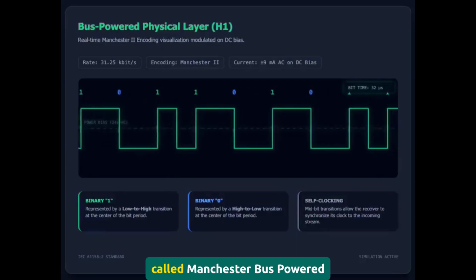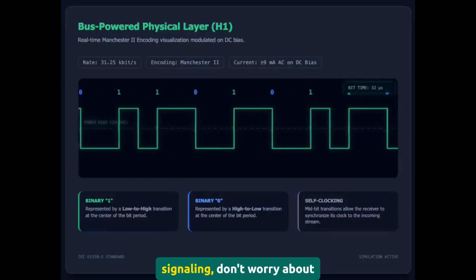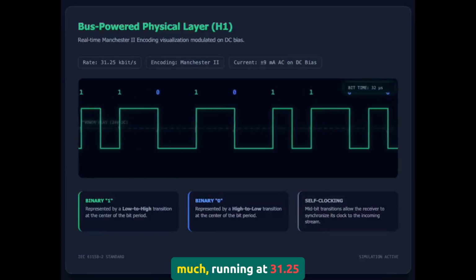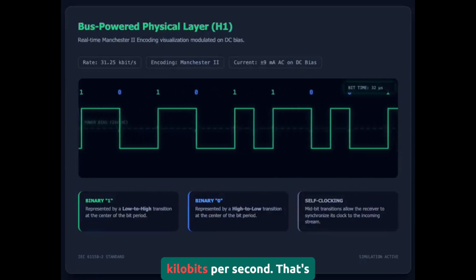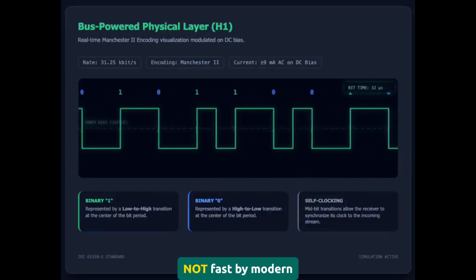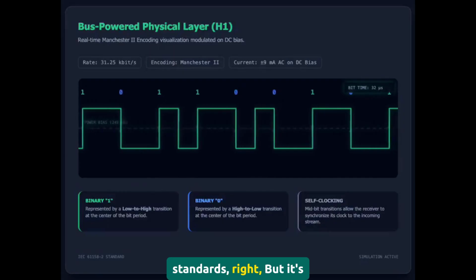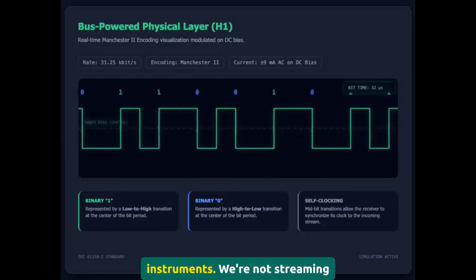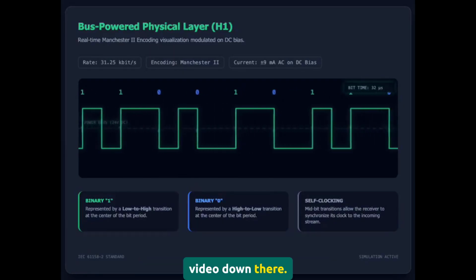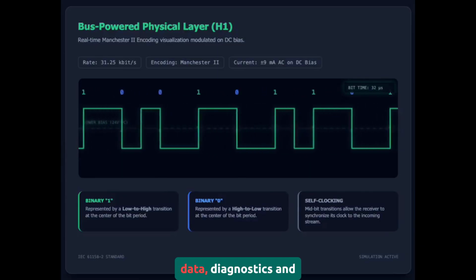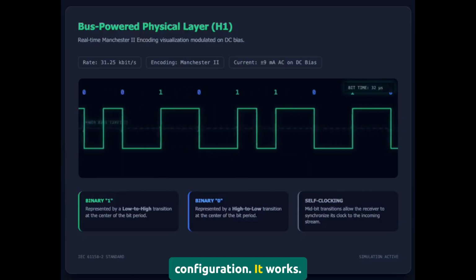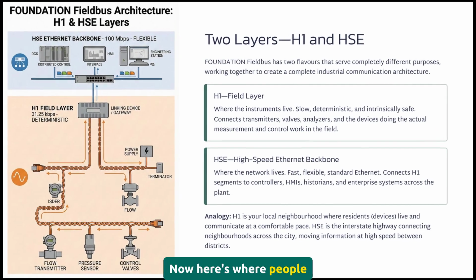The signals use what's called Manchester bus-powered signaling. Don't worry about the technical name too much. Running at 31.25 kilobits per second. That's not fast by modern standards, right? But it's fast enough for field instruments. We're not streaming video down there. We're trading control data, diagnostics, and configuration. It works.